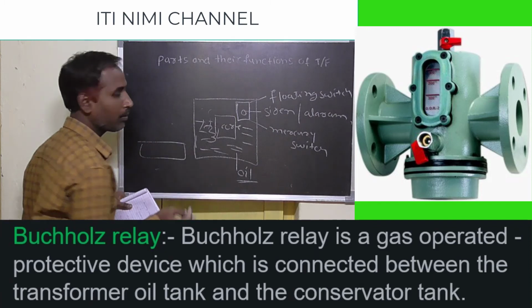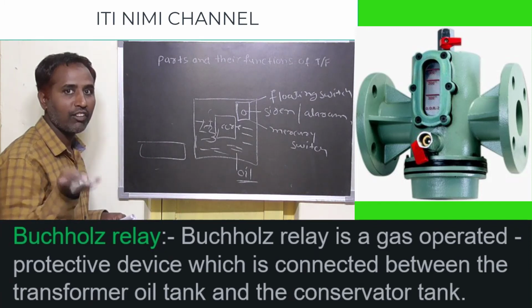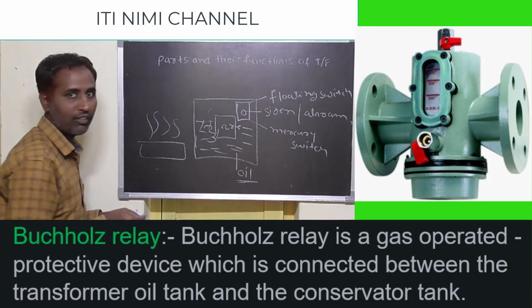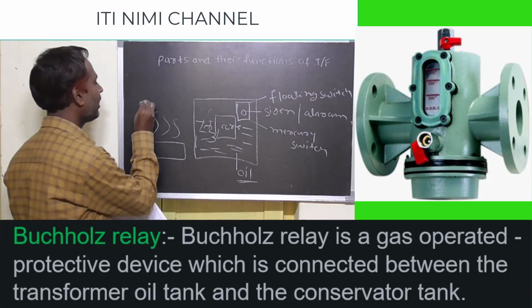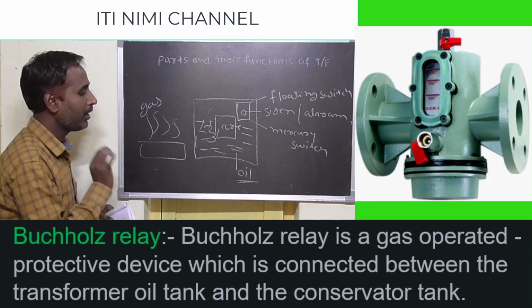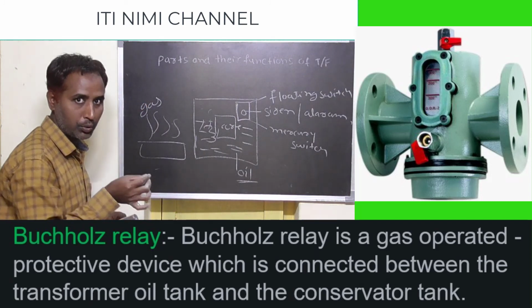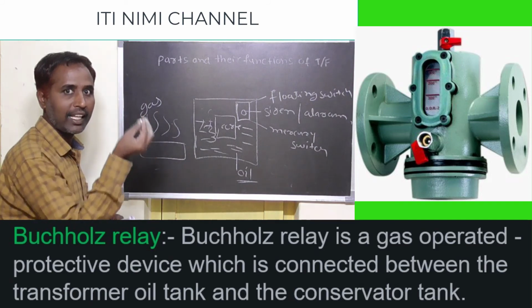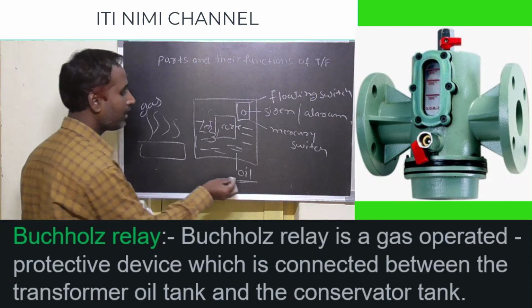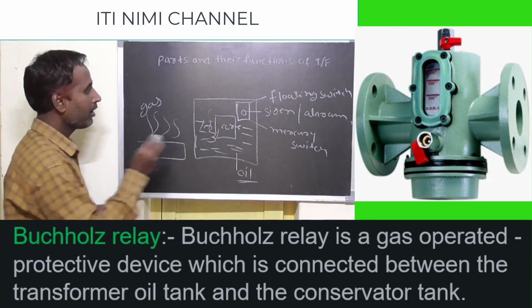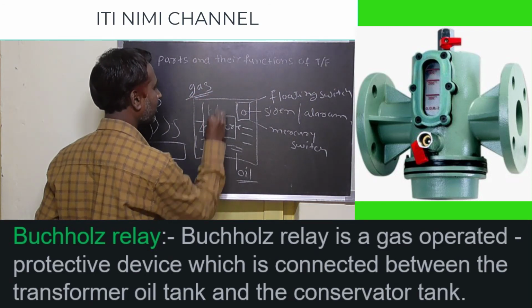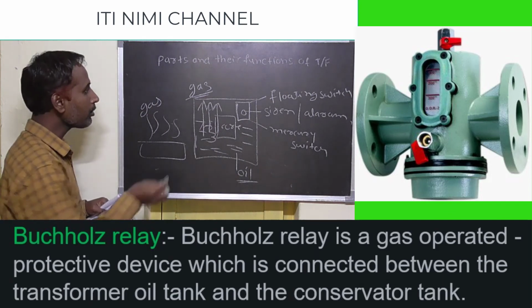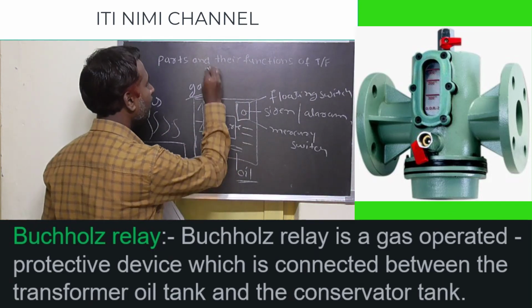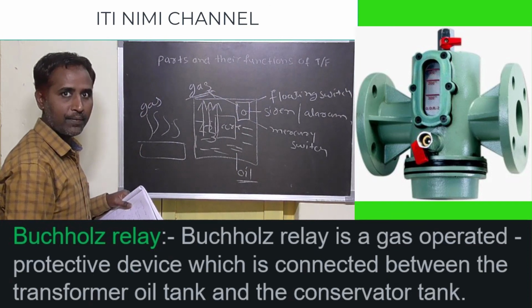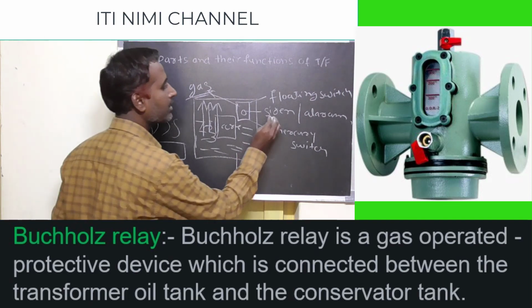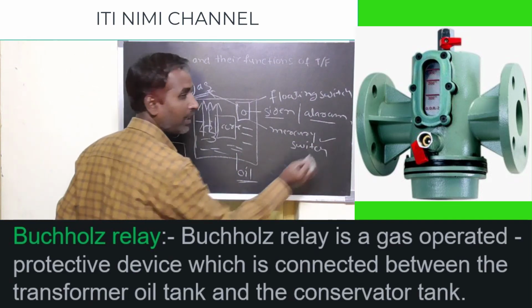What happens next - suppose if you boil water, fog or smoke comes out, like a gas forming. Similarly here, when the transformer oil is too heated, it evaporates and produces gas. The Buchholz relay detects this gas and operates, giving a siren or alarm with the help of the mercury switch.